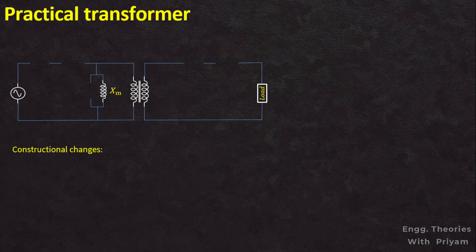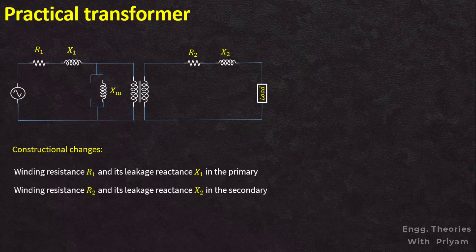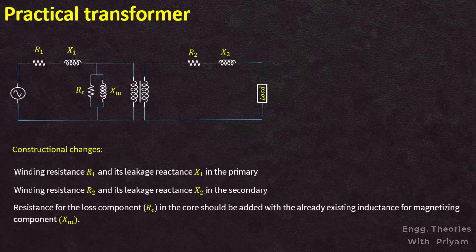There are some constructional changes that must be included. The first is that winding resistance R1 and leakage reactance X1 must be included in the primary winding, and winding resistance R2 and leakage reactance X2 must be included in the secondary winding. A loss component in the core, RC, must be added with the already existing magnetizing component XM.